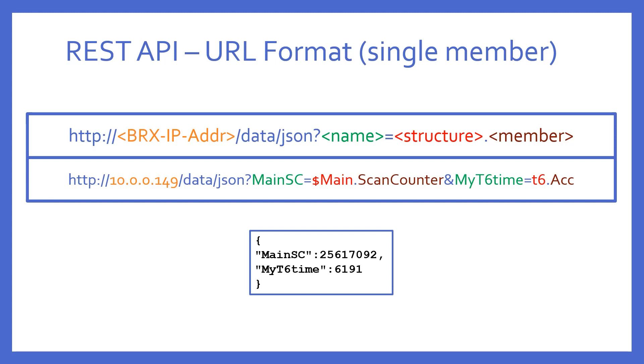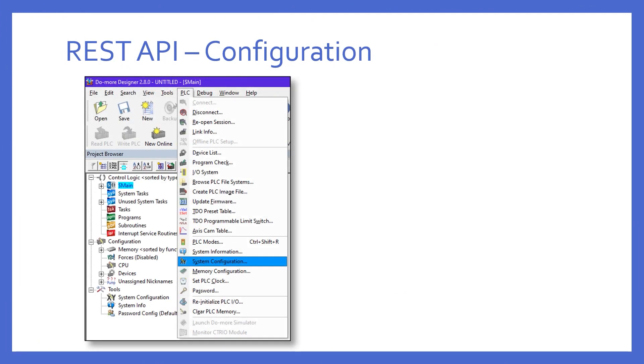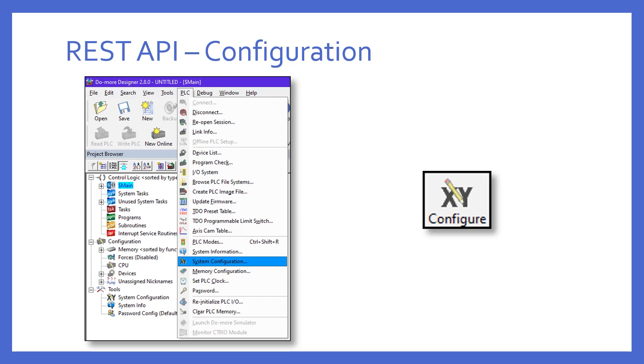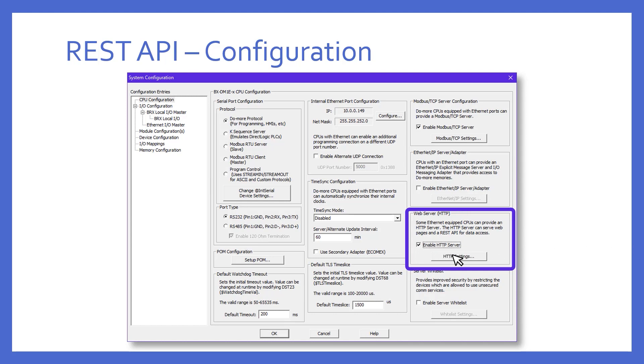So, how does one go about enabling this feature into BRX PLC? The REST API feature is not enabled by default. To enable, go to the system configuration, either via the menu, selecting PLC system configuration, or by pressing the configure button. And when you do, there is a small box called Web Server HTTP right here. You'll have to enable it, and then press the HTTP settings button to see more.